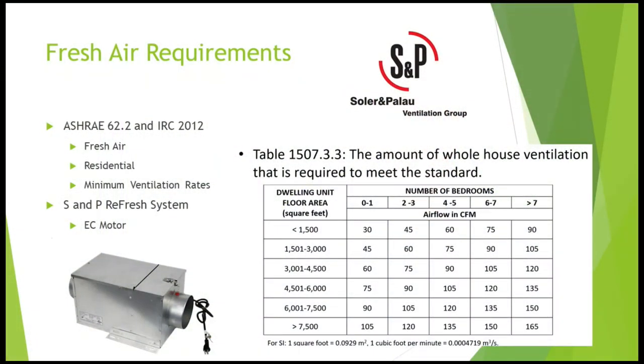We also talked about fans. So we had the air conditioning, now we have ventilation fans. Fans are a big deal now, especially with fresh air requirements—we're bringing in hot, humid air into the space, which means our AC systems have to increase in capacity. So we found a couple of unique ways of treating or exchanging that fresh air so we can get fresh air without increasing the capacity.